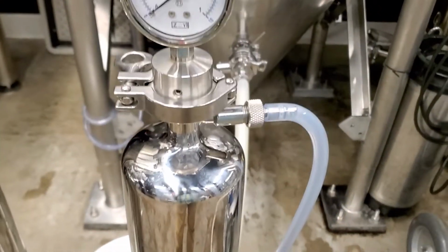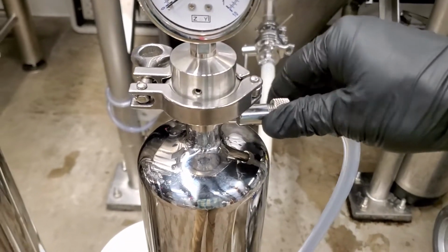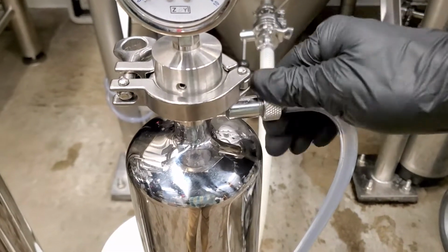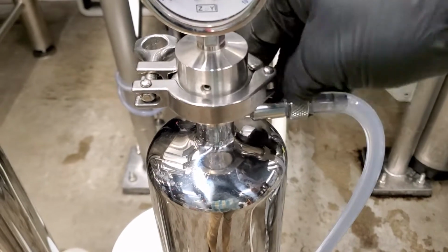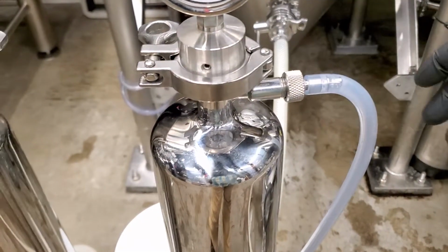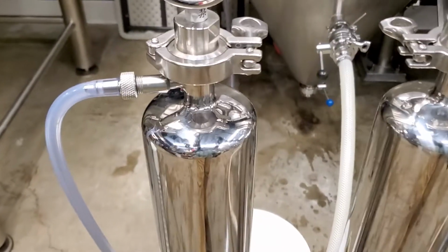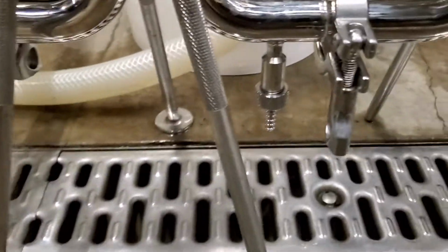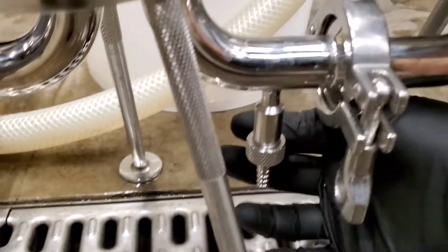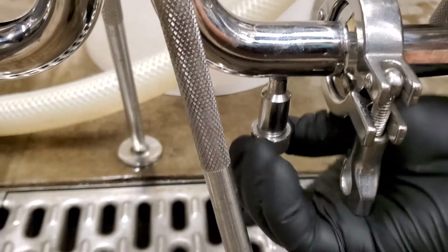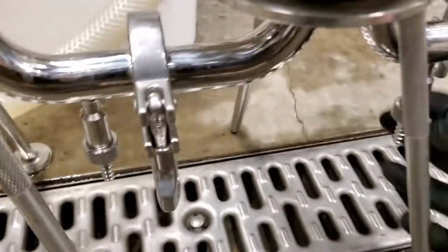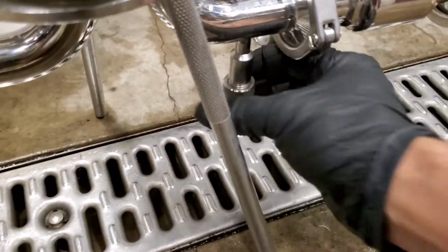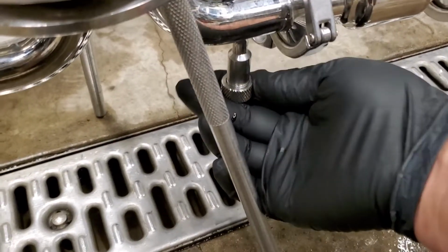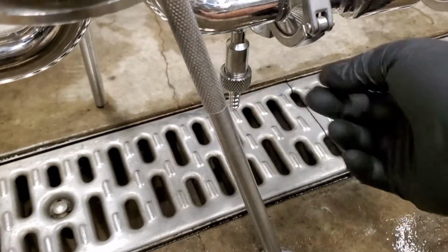We also want to make sure our first pre-filter, the 1 micron, is good to go, which it is - that's closed, that is open. So our 1 micron is slightly open, and our final filter, the 0.45, is slightly open. Those are good. Down at the very bottom of these cartridge chambers are the dump valves. I already tightened these up earlier, so always make sure to tighten those up and close them, because at the end of your sterilization process, you'll need to drain these chambers.